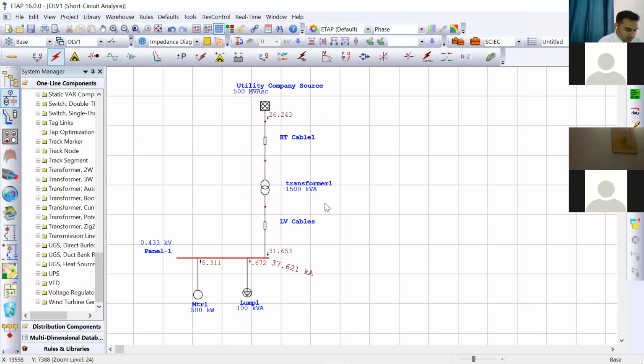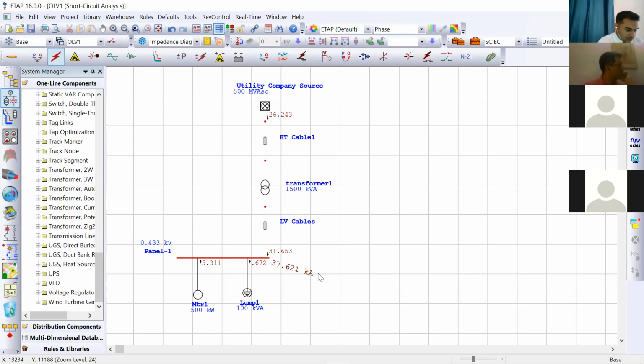So the answer is on the screen. Source is feeding 26.24 kiloampere current. On LV bus bar, we are getting 37.621 kiloampere current. Source is feeding approximately 31.653 kiloampere current on this LV bus bar. Lump load is feeding 0.672. See, lump load is a load which has got percentage of lighting load and percentage of motorized load.